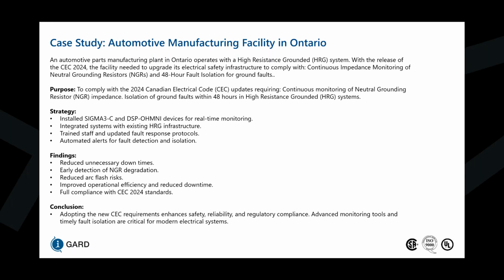So to comply with the 2024 electric code, they updated their resistor monitoring and installed a Sigma 3C, which has the 48-hour delay for resistor fault. They integrated systems with the existing HRG infrastructure, trained staff, and updated fault response protocols. That way they can go out and look for the NGR faults and provide corrective action for it during a downtime.